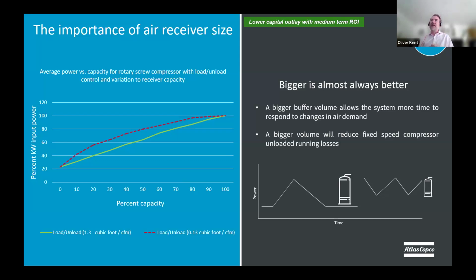When you look generally on a typical compressed air system, when you look at demand over time, it looks like the Himalayas. It's very variable. And so a compressor controller has to react to that constant changing in load. By introducing a larger air receiver, you slow things down. You add a lot more hysteresis to the system, and it gives the compressor controllers a lot more time to react to the changes in demand on your compressed air system. Also, if you've got fixed speed compressors, you will reduce drastically the amount of unloaded running time. If you've got variable speed drive machines, then you'll find that the variable speed drive machines have got a lot more time to react to changes in the flow.